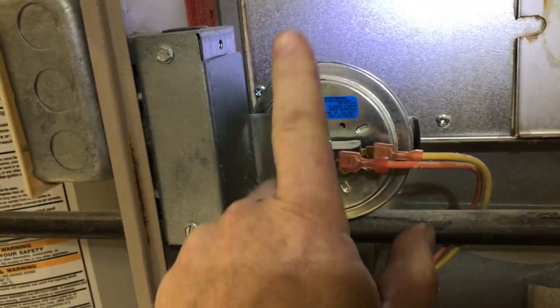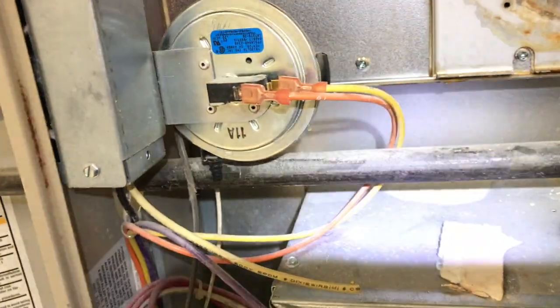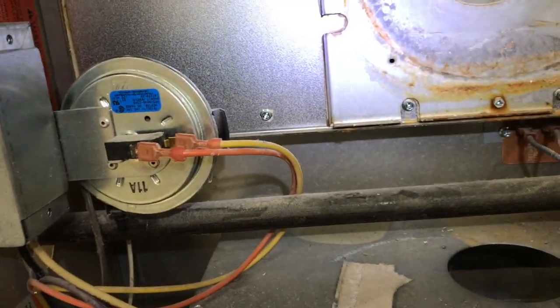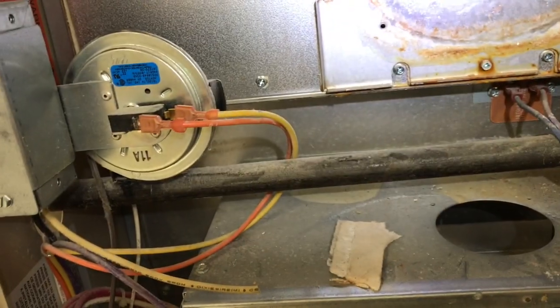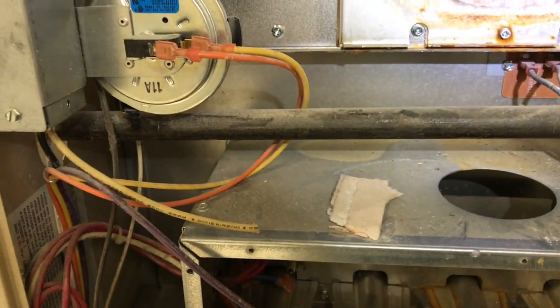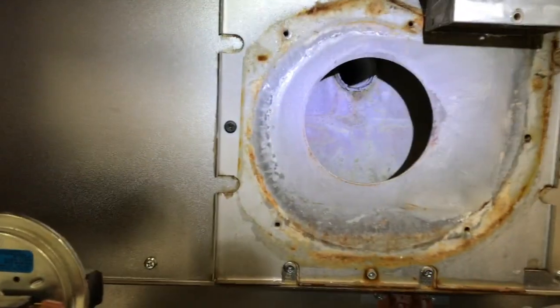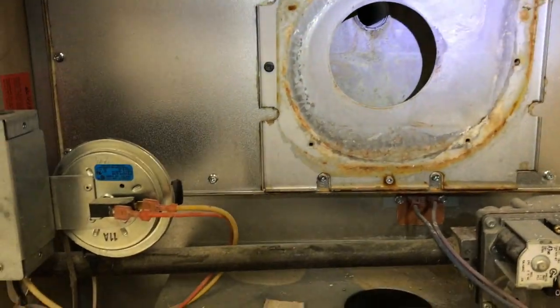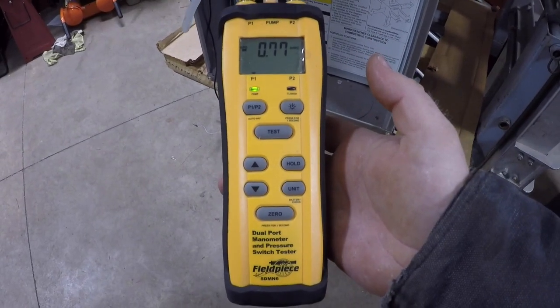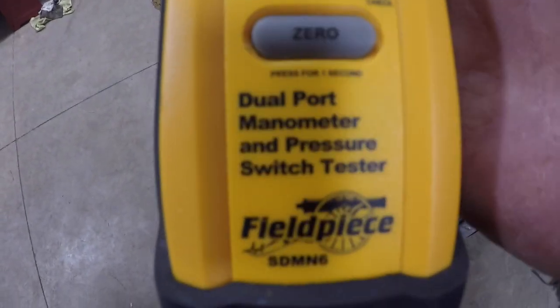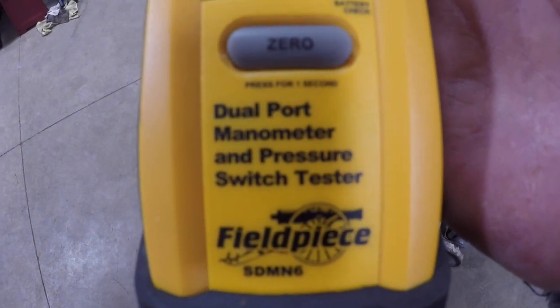So I'm working on a 125,000 BTU Amana. When I first got here, the pressure switch wasn't making. So I thought, oh, well, the pressure switch is bad. But I ended up taking out my pressure tester, which I'll grab here, and I found out that the inducer motor, which is normally right here, wasn't making enough draft. So this is the tool that I use when I have a pressure switch issue. It's a dual port manometer and pressure switch tester.